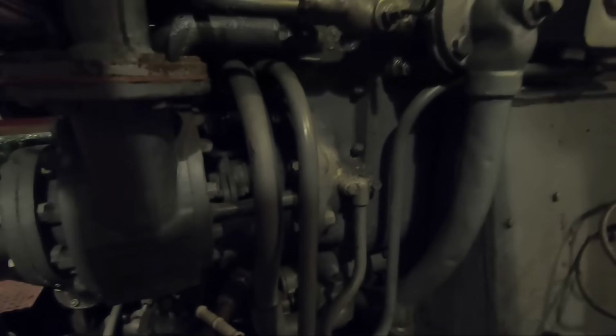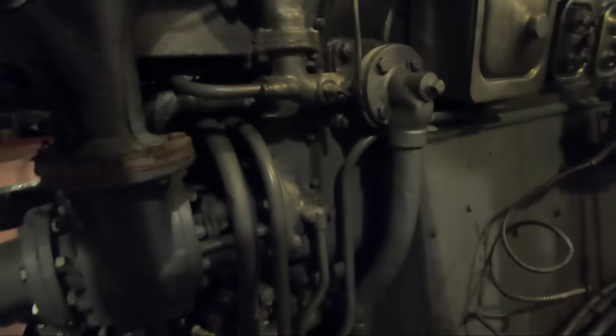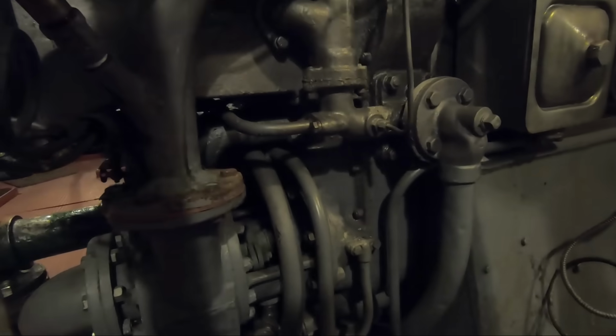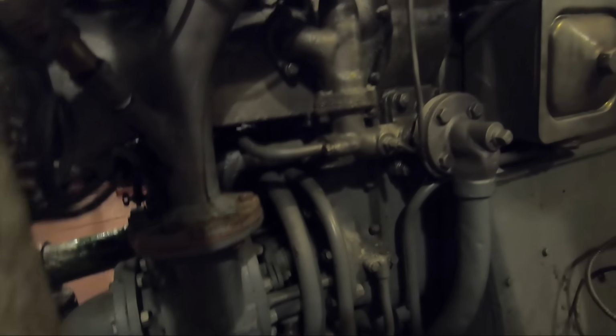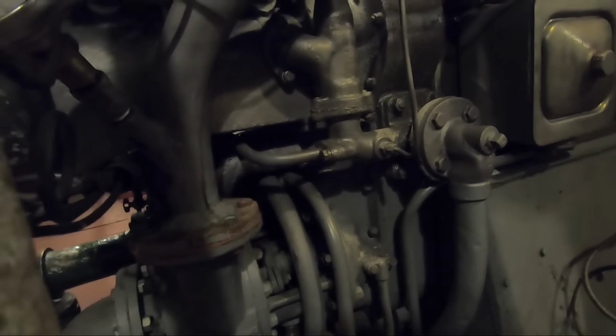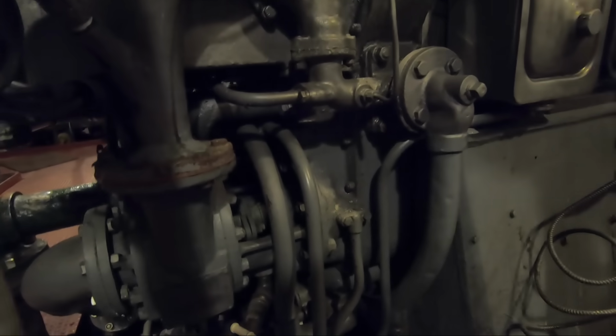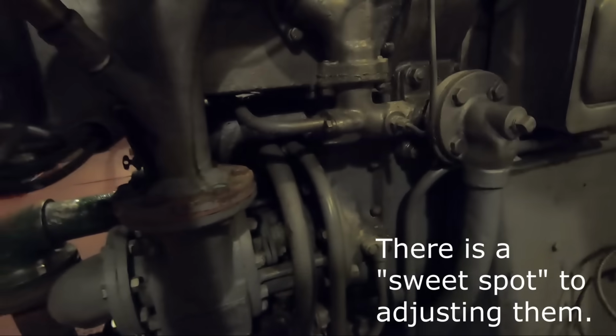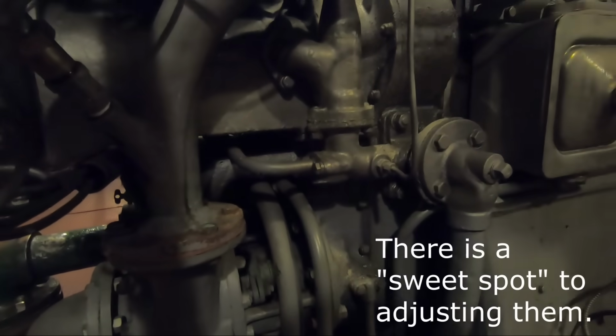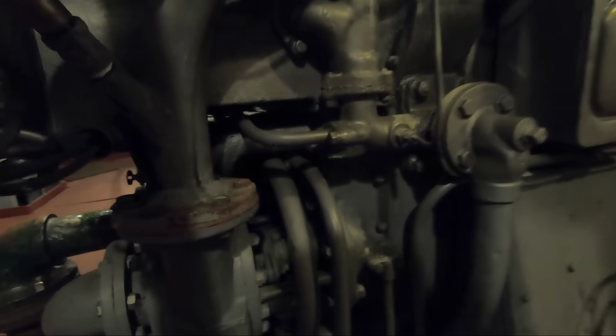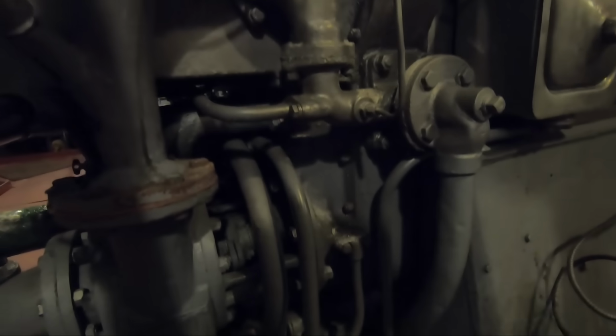So the packing gland here, they are designed to leak. They leak a little bit, and they do that so that the packing stays wet, swelled up, and basically watertight. However, there's only so much you can tighten these things up. If you tighten them too much, they stop leaking, and then they start to burn up and smoke because they're not being lubricated and cooled.